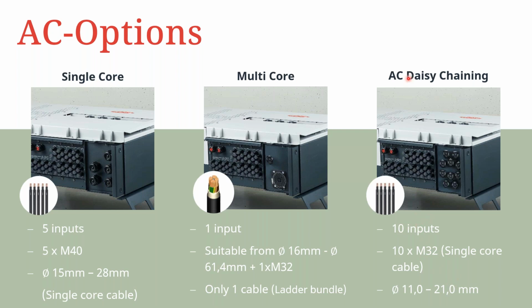You can also order an AC daisy-chained version, meaning that this can allow you to save on things like AC disconnectors for the inverters, because the inverter can be used to loop AC power from one inverter to the next, as we're going to see in the next session. And therefore, in this particular case, the cable size is limited to 11.0 to a maximum of 21 millimeters in diameter for the cable glands that are provided here.